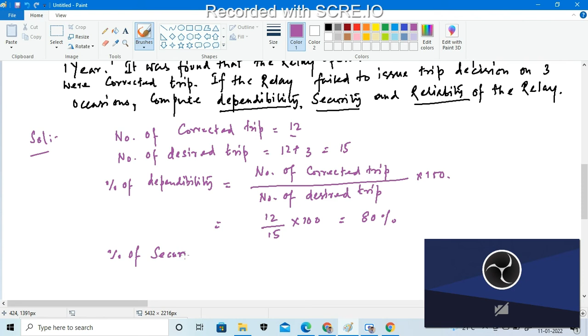Now the percentage of security. What is the formula? That will be the number of correct trips divided by the total number of trips, into 100. The number of correct trips is 12 and the total number of trips is 14, since the relay operated 14 times. Into 100%, that is equal to 85.71%.